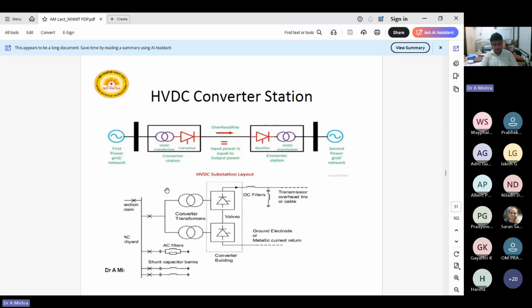The major components are the converter transformer and then the valve. Valve means the devices, either thyristor or IGBT; they are called valves. Then on the AC side you will use an AC filter, and on the DC side you will use a DC filter. Why? Because, as I just told you, if you are using a power electronics based system, harmonics will be generated in the system. That harmonic should not affect our main system. For that purpose, filters will be required at both ends, the DC side and the AC side.